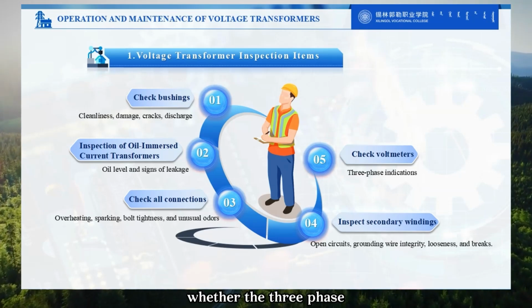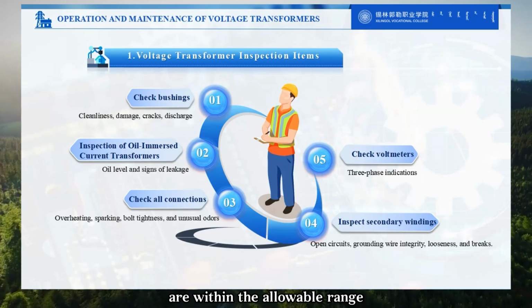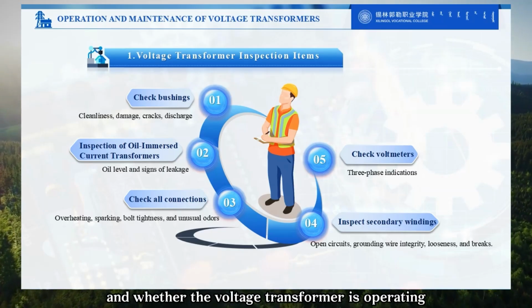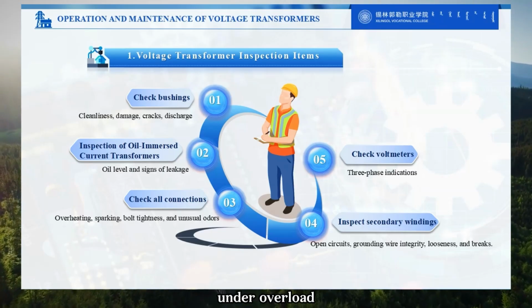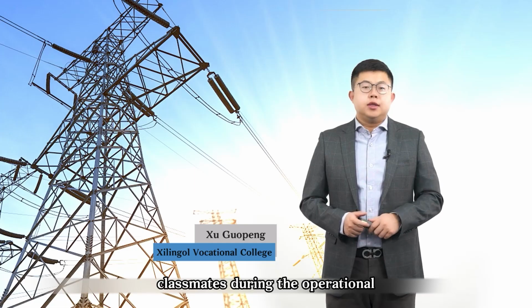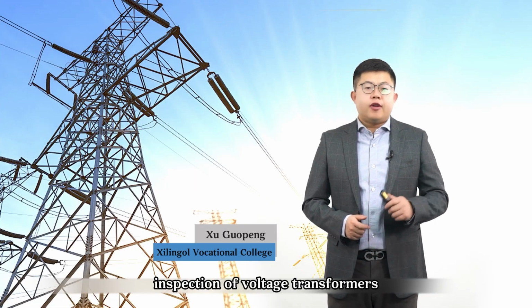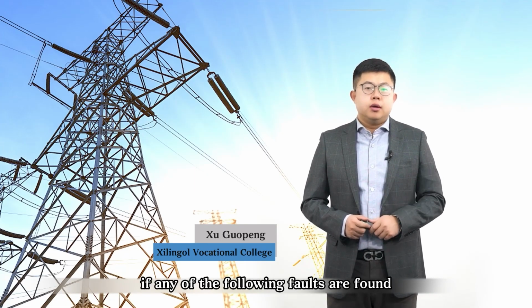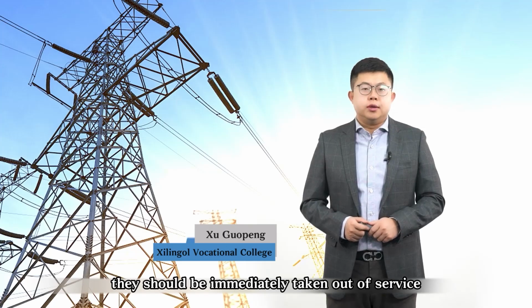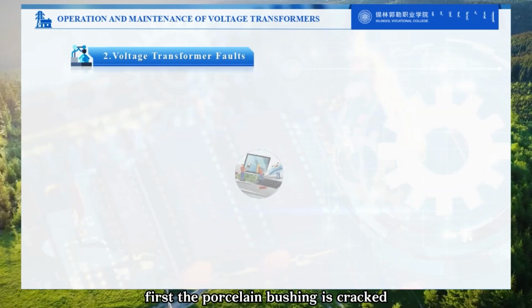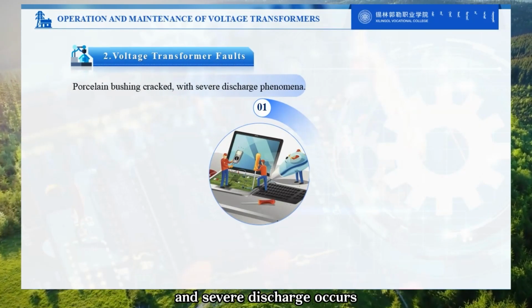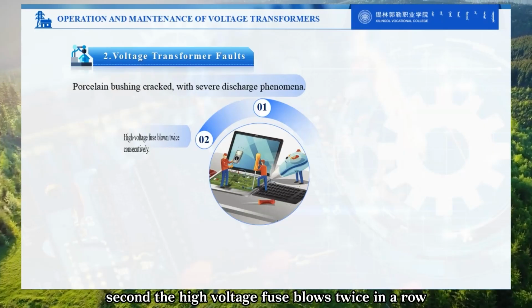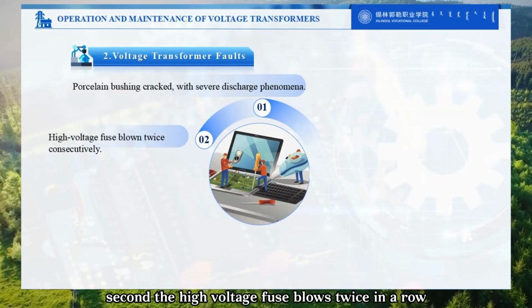Fifth, check whether the three-phase indications of the voltmeter are within the allowable range and whether the voltage transformer is operating under overload. Classmates, during the operational inspection of voltage transformers, if any of the following faults are found, they should be immediately taken out of service. First, the porcelain bushing is cracked, and severe discharge occurs. Second, the high-voltage fuse blows twice in a row.